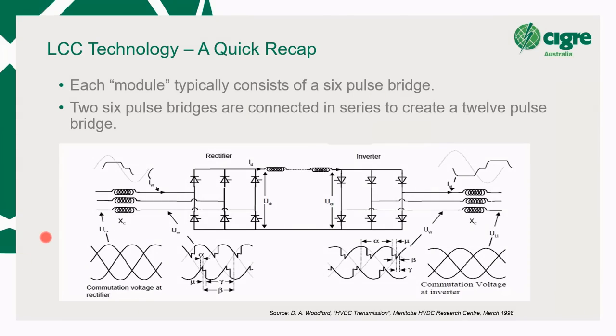A typical LCC, of normal, not the extreme converters, will be a 12 pulse bridge. They have a 30 degree phase shift between each of the six pulses, and that's achieved through having two transformers, a star and a star delta connected in series.